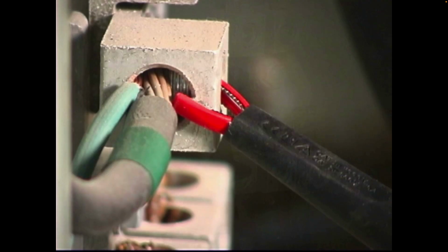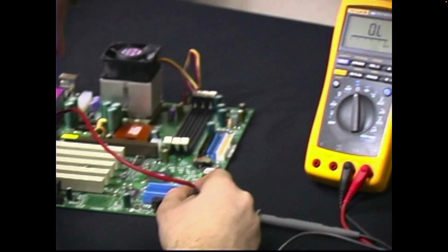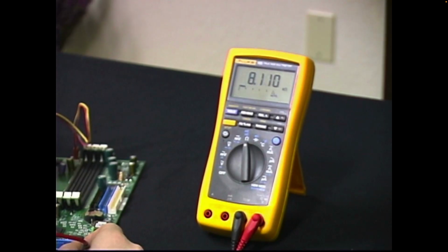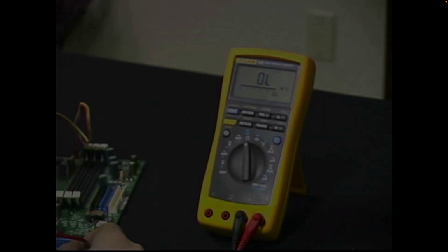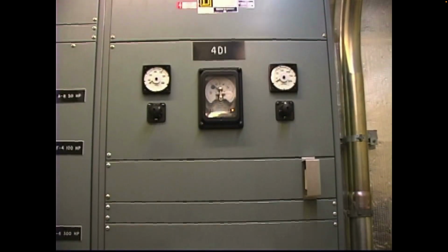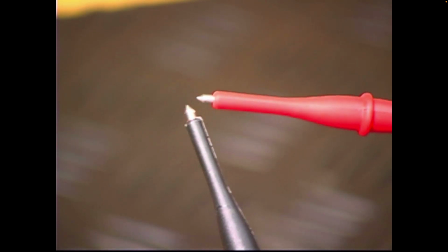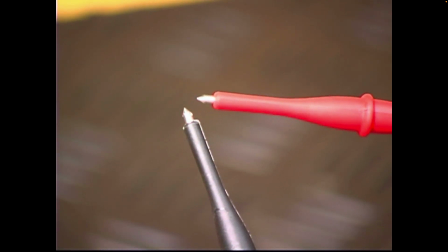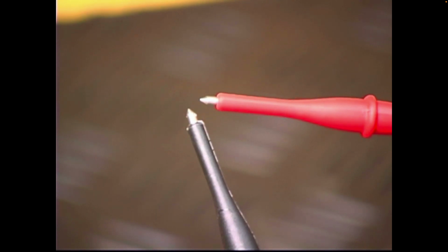Remember, test probes are designed for a variety of test environments. What is appropriate for a circuit board in a Cat 1 environment may not be appropriate for 480 or 600 volt circuits. In a high energy setting, make sure your test probes have a minimum amount of exposed metal. This will help avoid creating a short between two phases if your hand slips off the probes.